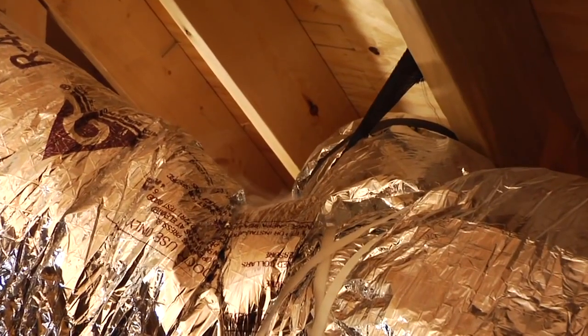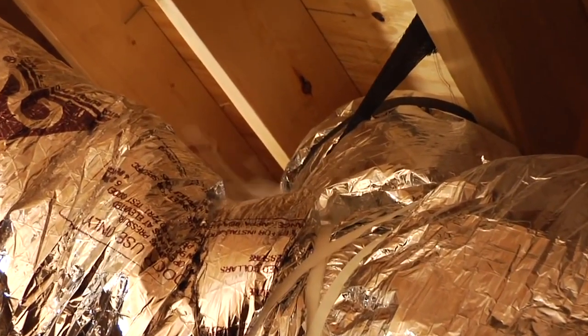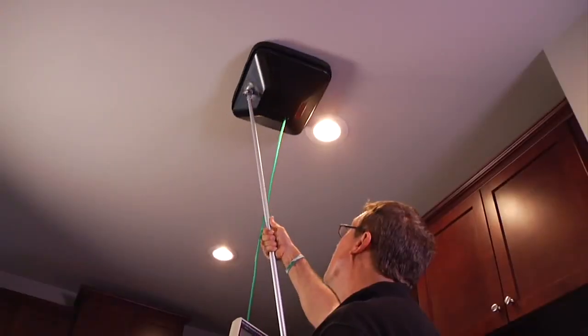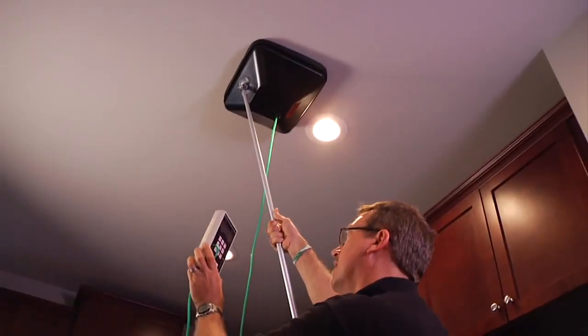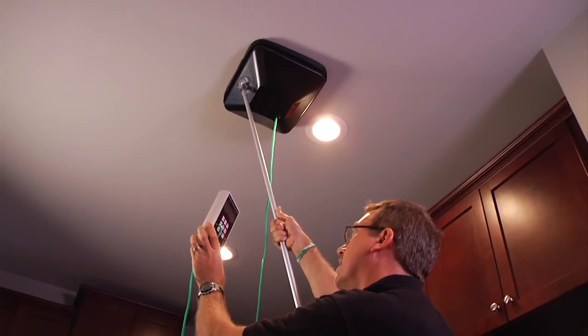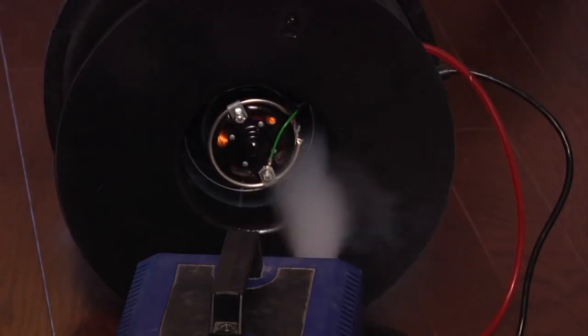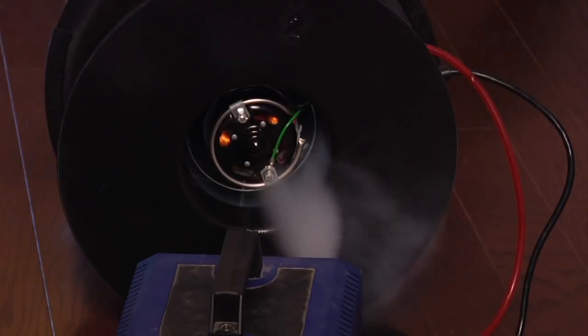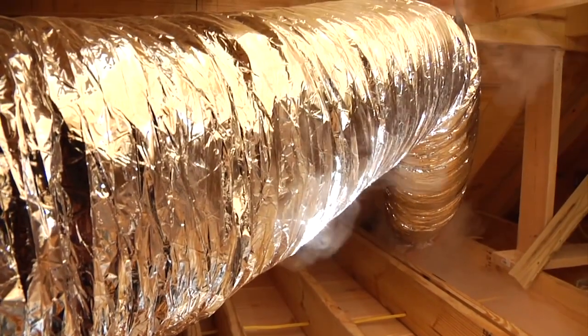If the duct system is not up to par, we can leave the duct blaster running and use a smoke stick to find leaks in the ductwork. Once you have determined your results, compare them against the Energy Code or Green Building Program requirements that you are hoping to certify under. A visual inspection of the duct system can go a long way in explaining test results. Pressure pans can also be used with a blower door to help locate which duct runs have the most leaks. And finally, a theatrical fog machine can be used in conjunction with a duct blaster to identify problem areas.